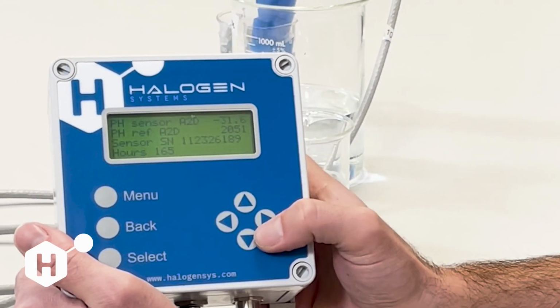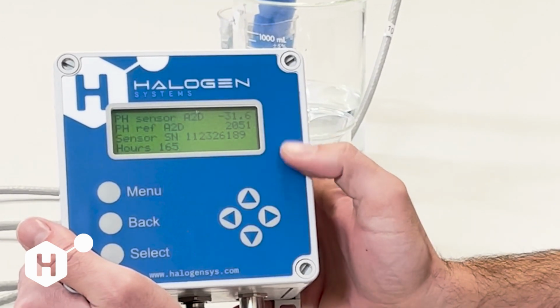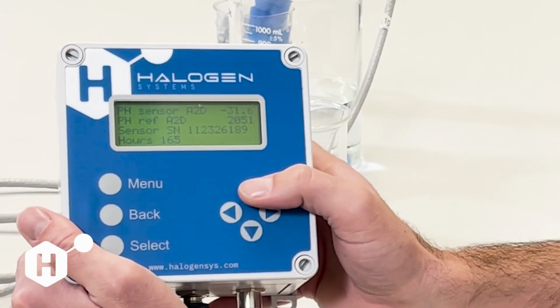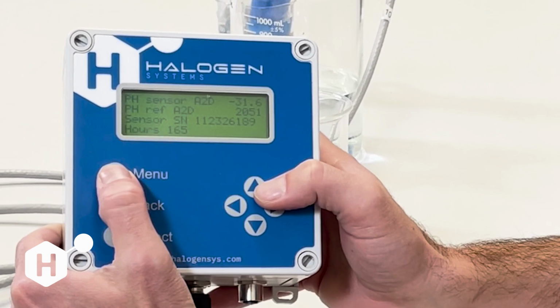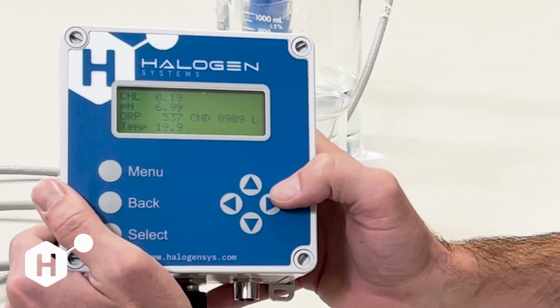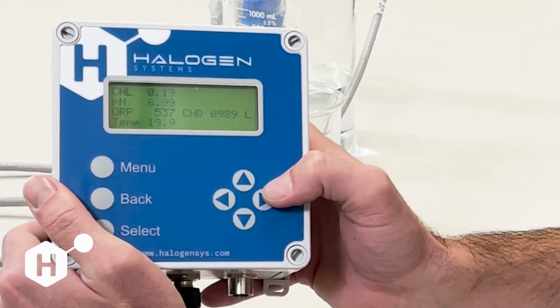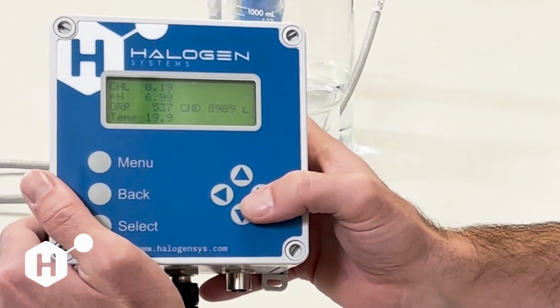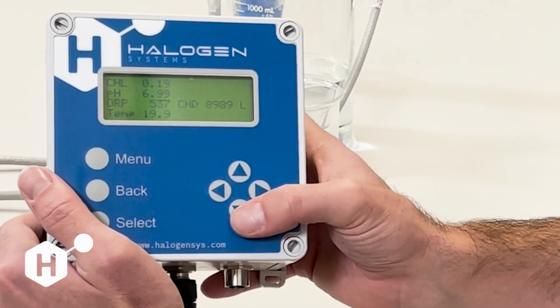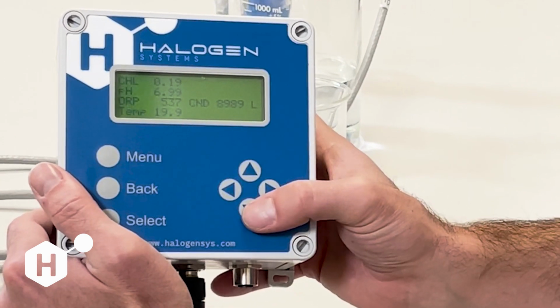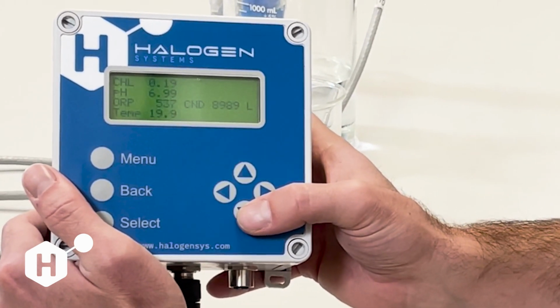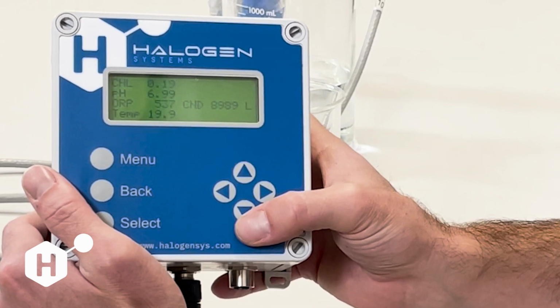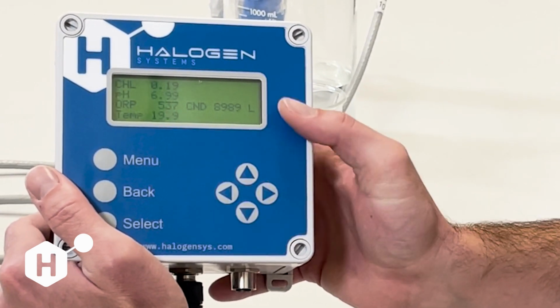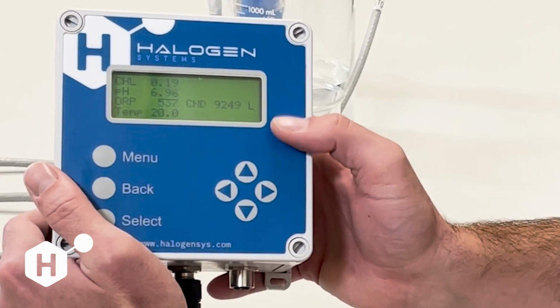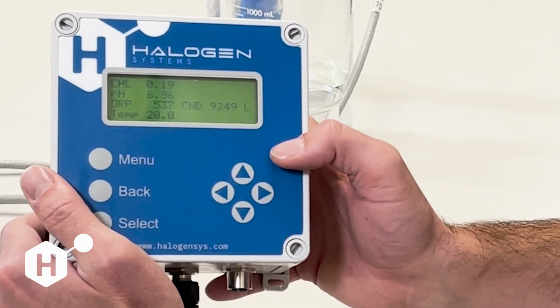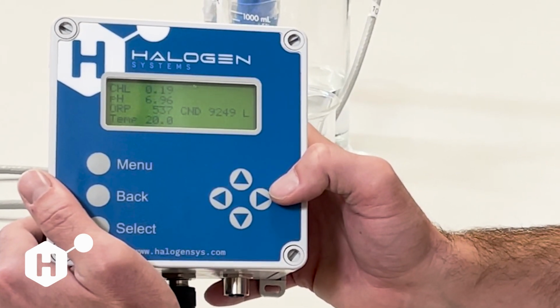So we're continuing to monitor our pH millivolts in 7 buffer, and our pH millivolts are still close to where we did our calibration. So we're going to go ahead and double check on our reported pH and see that, yep, it is just about 7. If it's 7 plus or minus 0.05, that's usually acceptable to me because we might be applying a temperature compensation. All of our pH calibrations are expected to be done at 25 degrees Celsius. So if we have a little bit of a temperature difference, you might see a slight difference in the reported pH because we're applying our temperature compensation.